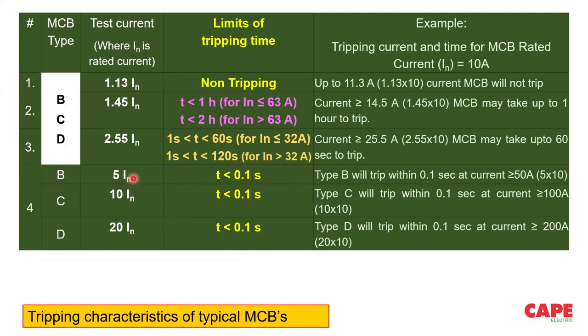A type B MCB requires up to 5 times, or anything above 5 times, the rated current, and it will disconnect in 0.1 second. Type C, 0.1 second, means it needs 10 times the current, and type D 20 times the current. So we discussed this subject in the last part of the webinar. Our problem which we face in the market is the type B MCB. A type B MCB with the 5 times disconnection current is actually required to protect the final circuits, for example in a residential building, or let's say in a hospital where multiple devices are used.